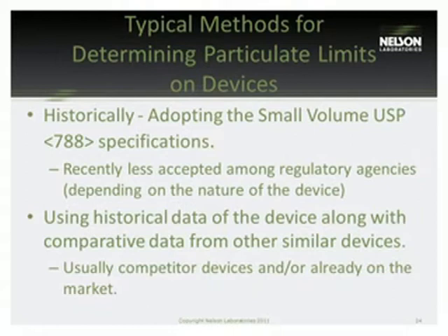Using historical data of the device along with comparative data, which we'll go into more detail on both of those, of similar devices is also an excellent way to determine a method and particulate limits for your device. Often this is comprised of taking a competitor device that may already be on the market, performing testing on that device similar to the one you're testing, and then comparing the particulate matter data to both samples, the one that's currently on the market and the one that's in development, to see where you're currently standing.